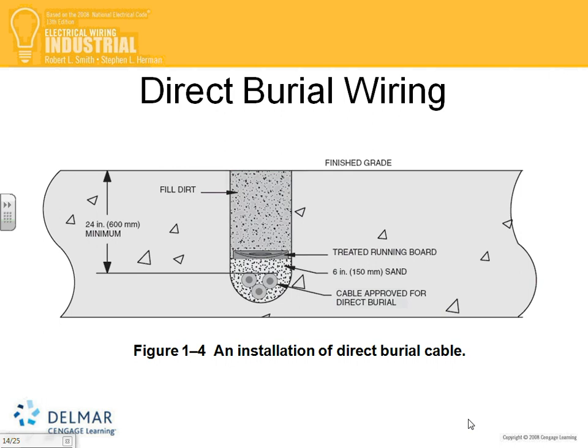Here's another one, guys. Detail for direct buried cables. I like these details. 24 inches is typical, depth above your direct buried cables. Warning tape. When do I need warning tape, guys, in this area?